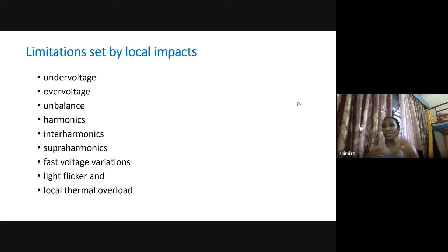Then harmonics. This charger is AC and you have to convert to DC, so a rectifier is there. Whenever a rectifier is there, you will have harmonics. If it's single phase, the third and fifth harmonics will be dominant. If it's three phase, the 5th, 7th and similar harmonics. Again, it depends on the type of converter used. If it's 6 pulse, the 5th and 7th will be high. If it's 12 pulse, the 11th and 13th will be high. So these harmonics will be injected into the grid.